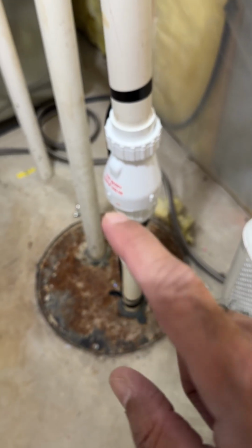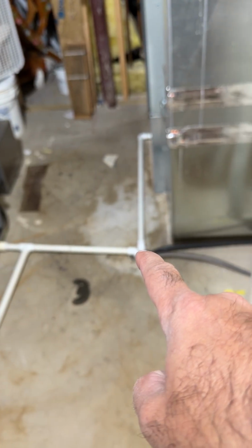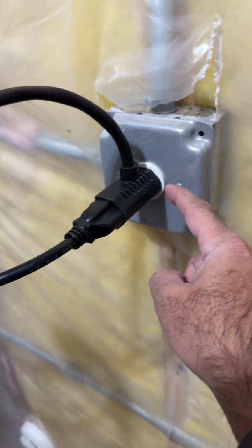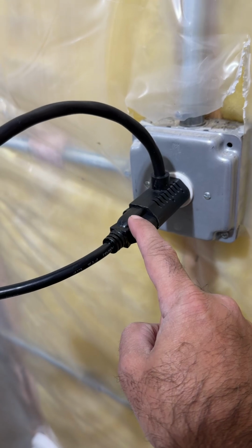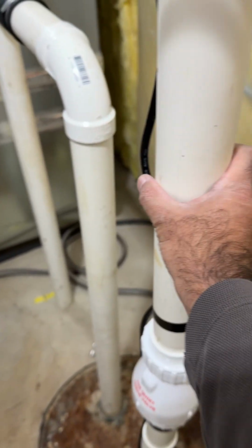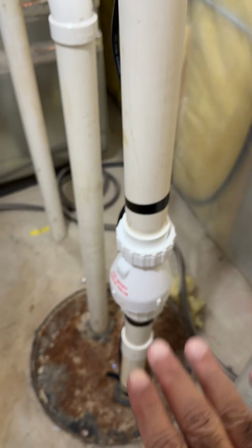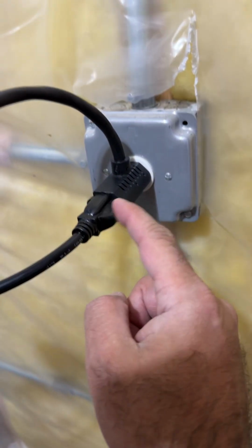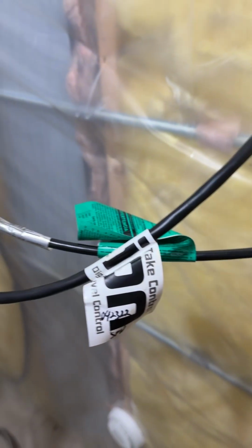So again, here's your quick fix. Water comes out of the drainage pump. Over here, unplug the switch from the motor to test whether the motor and the pump itself is working. Directly plug this in. If you hear and feel everything moving up, then you know that's working. Let that cycle and drain the water down. You'll see the water start to lower inside the drain. Fill it up again and see if that clears, and maybe that toilet paper or that obstruction has been cleared, and everything should be okay. Then plug the switch back in. If the switch starts to work again as the water level starts to rise, then you've cleared the obstruction.